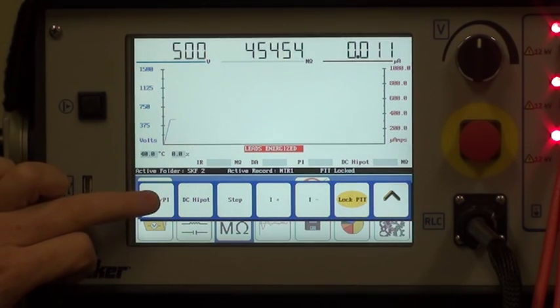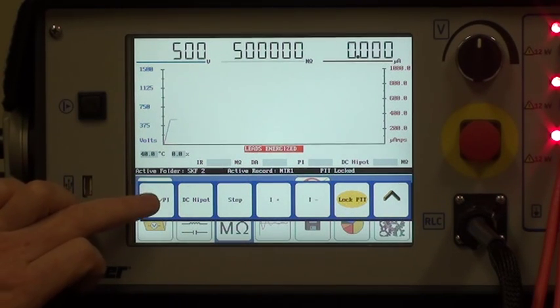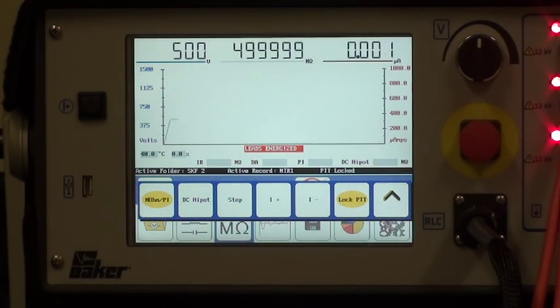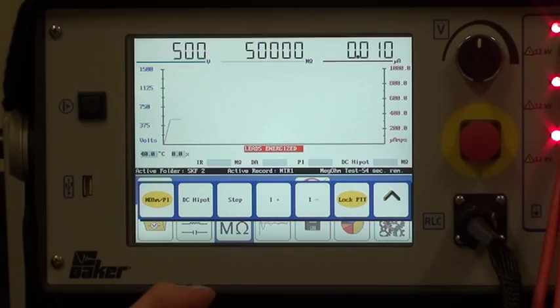What I'm now going to do is activate the megaohm stroke PI polarisation index button. What this does is it starts a countdown. This countdown is a standard IEEE test for a megaohm for 60 seconds.